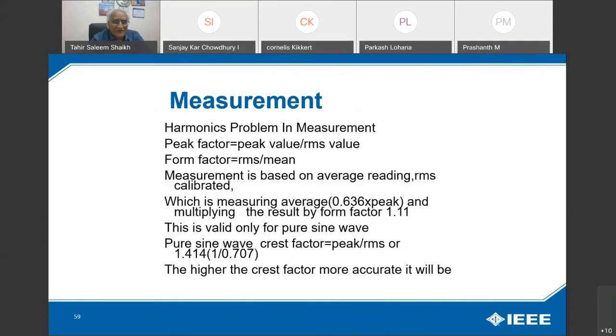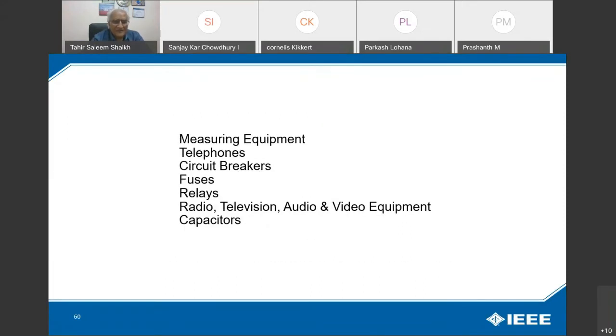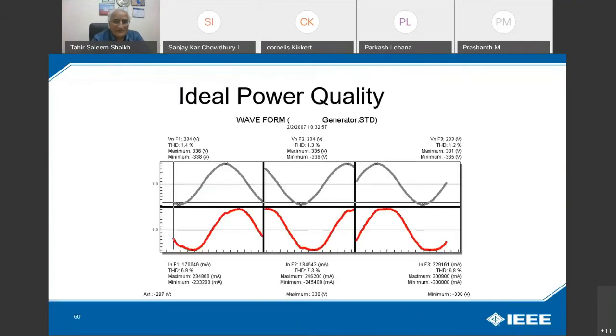Measurement, you can have problems in measurement: peak factor, peak value, form factor. RMS measurement is based on an average reading, and this will give a wrong reading on your meters. Measuring equipment, telephone, circuit breaker, fuses, relays, noise tripping of fuses and relays, radio, audio and video equipment, capacitor. Even I have seen in certain hospitals the harmonics create so much noise, tripping and image distortion in ultrasound labs. So you have to correct this.